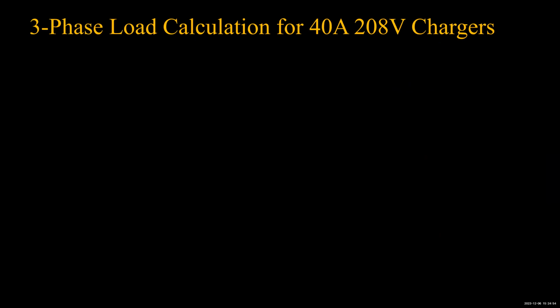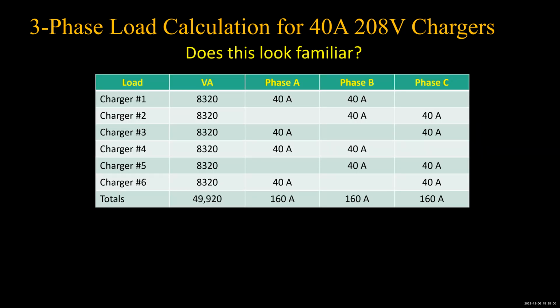3-phase load calculation for 40 amp 208 volt chargers. Let's do it. Very exciting. You might try it like this. Here's one you're going to connect across phase A and B. Another one goes to B and C. Next one is C to A. And on, just like that. And sure enough, you add them up, 160 amps per phase, 49,920 volt amperes. Why? Because each one is 8320, and you add 6 of them, that's 49,920.